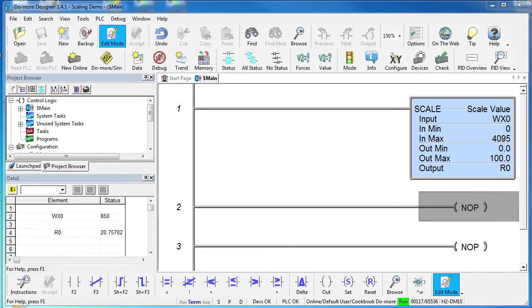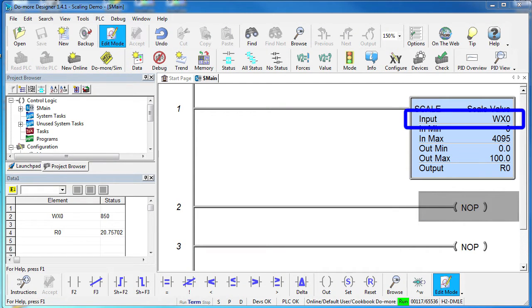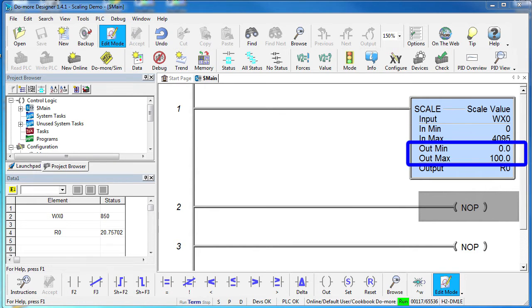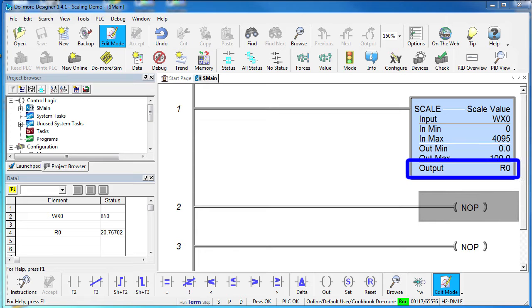Here's what that looks like in the Do-more code. We have an analog input coming in on port WX0 whose range is 0 to 4095. We want that to be scaled to 0 to 100 inches and then put that result in R0 which is a real register.